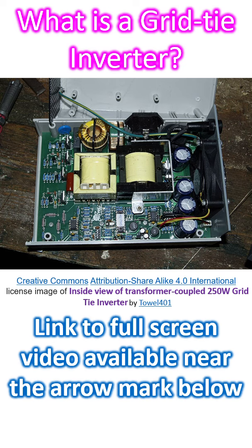They must accurately match the voltage, frequency and phase of the grid sine wave alternating current waveform. Phase angle should typically be within 1 degree of the grid waveform. Internal circuitry of the grid tie inverter senses the grid waveforms and outputs an alternating current corresponding to that.